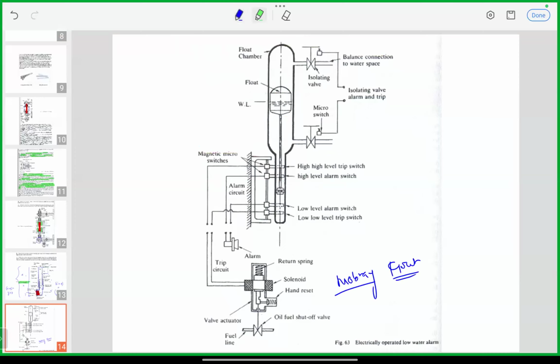This is fitted in addition to the gauge glass, not before it, because the gauge glass alone cannot give you an alarm. So for low level alarm, high level alarm, and trip functions, an additional system has to be incorporated.